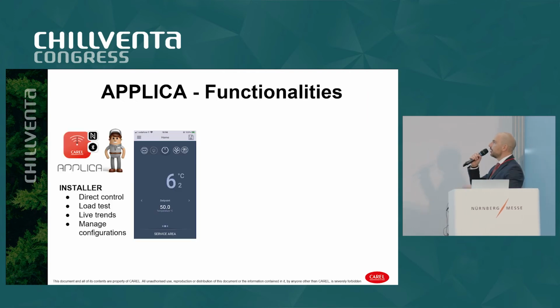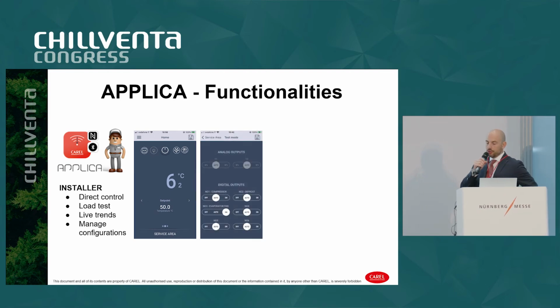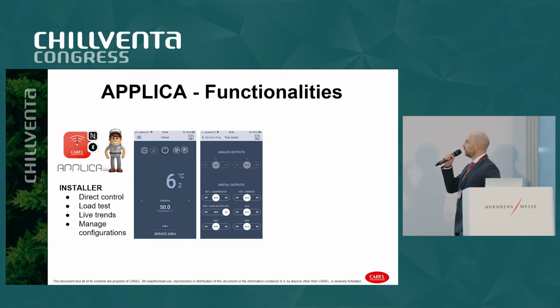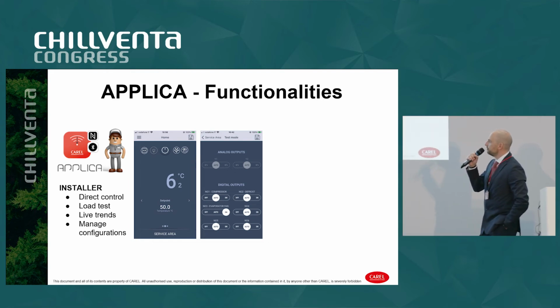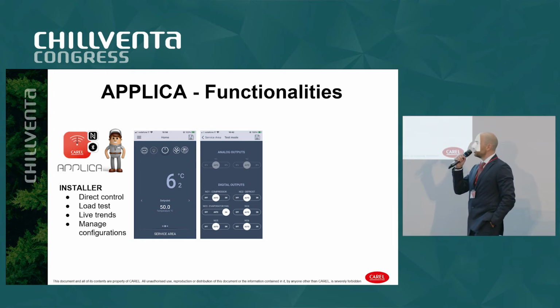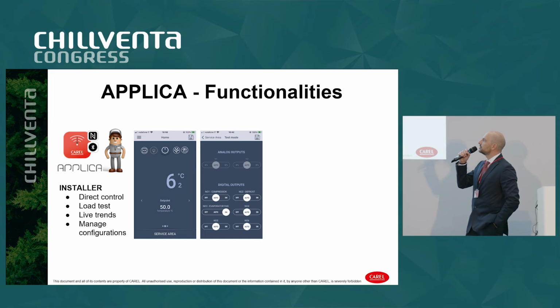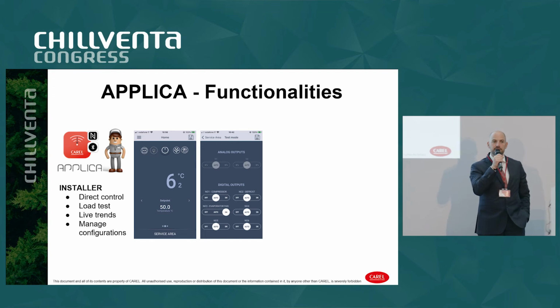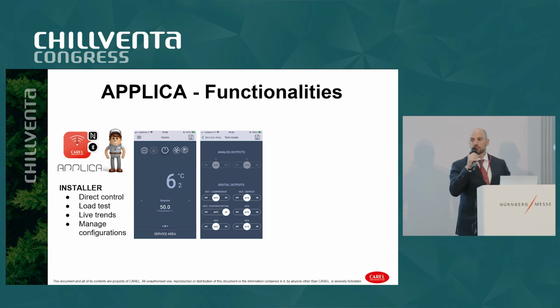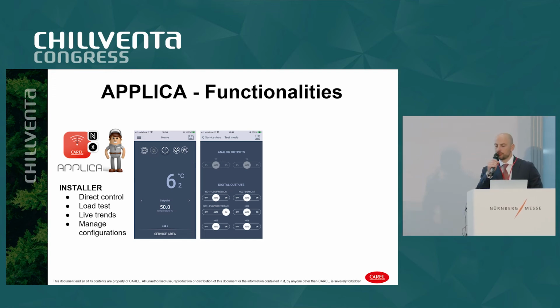What else does Applica allow you to do? Basically, direct control of the controller. It lets you test if the connection has been made correctly, because you can activate the compressor, stop it, or do the same for defrost and for the evaporator fans, so you are 100% sure the cabling is correct.